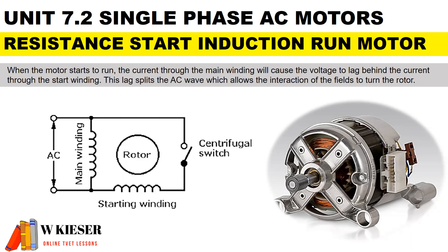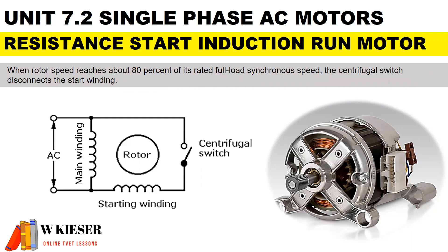When the motor starts to run, the current through the main winding will cause the voltage to lag behind the current through the start winding. This lag splits the AC wave, which allows the interaction of the fields to turn the rotor. When the rotor reaches about 80% of its full-rated synchronous speed, the centrifugal switch disconnects the start winding.